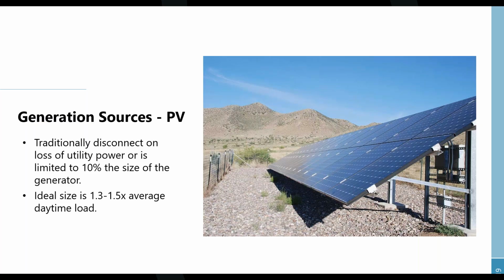So traditionally, when you're running on a generator, you need to turn off all PV generation. Otherwise, the PV system can backfeed into your generator alternator and damage it. So with a traditional system, the rule of thumb is you have to disconnect PV unless it's under 10% of the size of the generator. But with a microgrid controller, you don't need to do that because it's monitoring power flow and can prevent damage to your microgrid components.